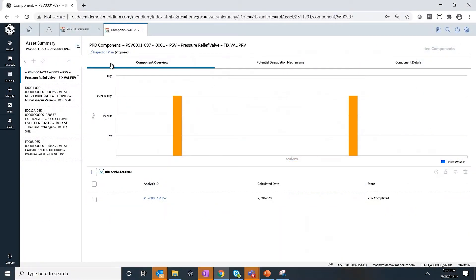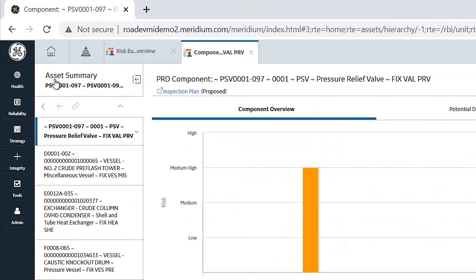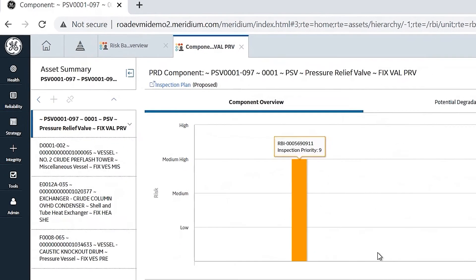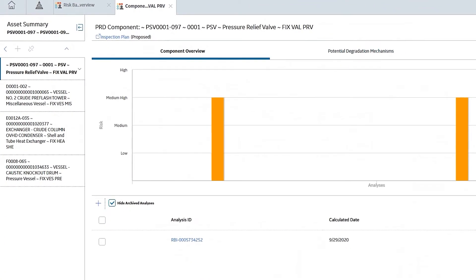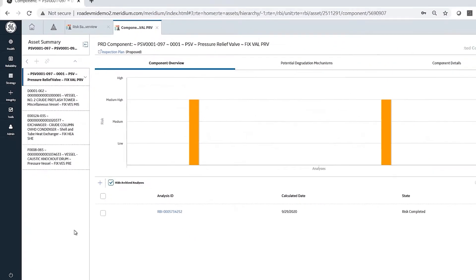Now, I've logged into APM and I am sitting on a pressure relief device — a PSV — and this is an RBI view for that. This is the component details where you can see the damage mechanism associated with it and all the analysis that is done. When you select a PRD component, you can also see all the equipment which it is protecting. At times, you can have one pressure relief device between multiple assets.